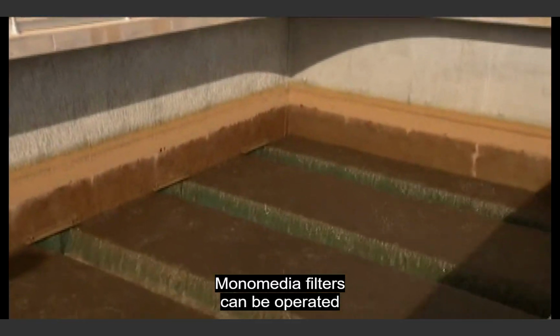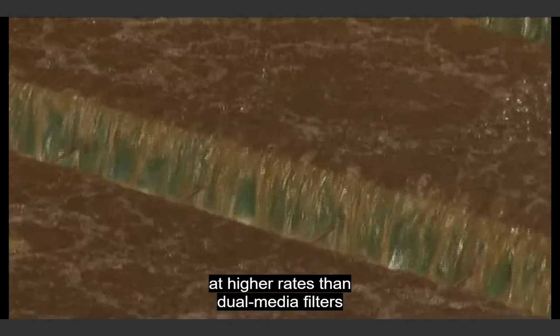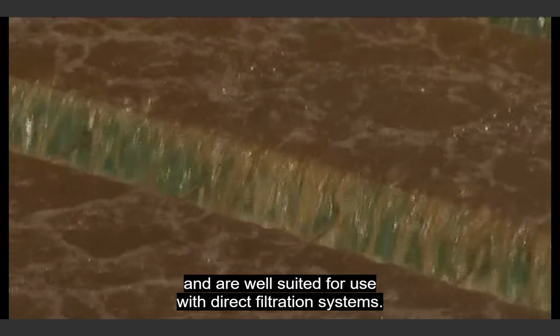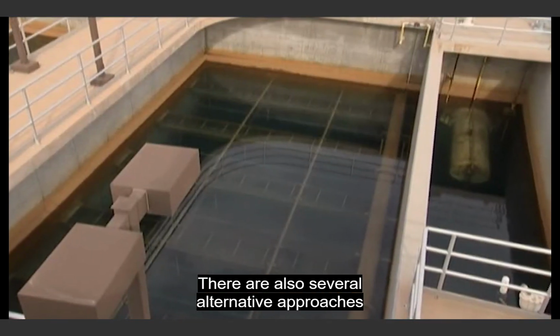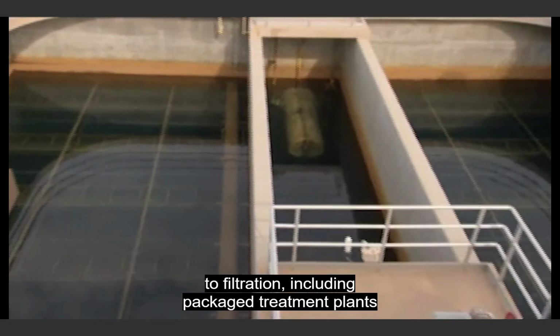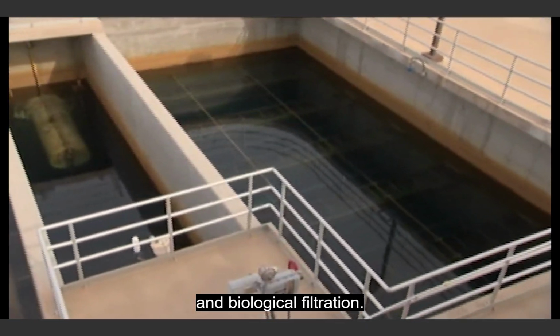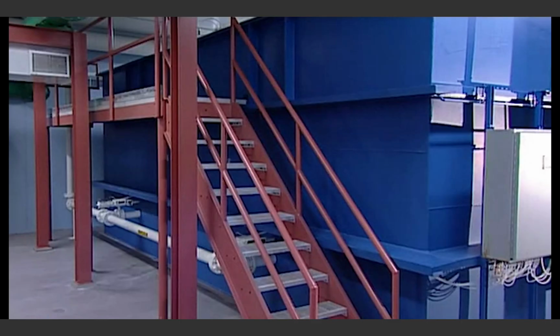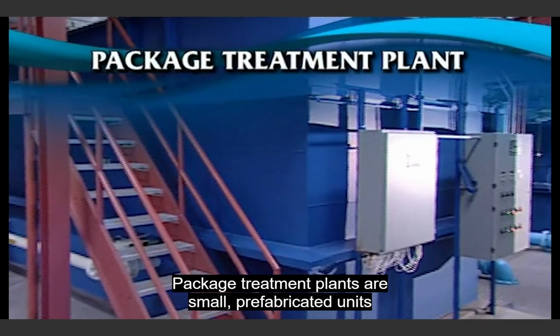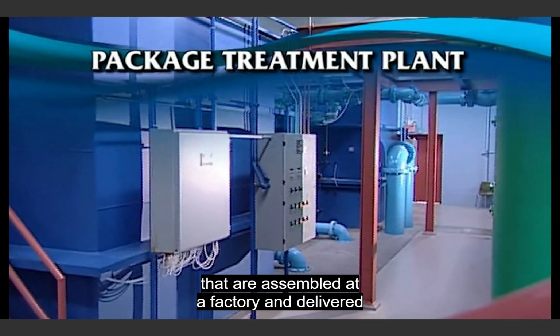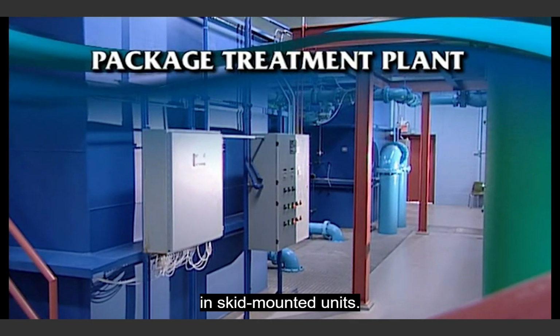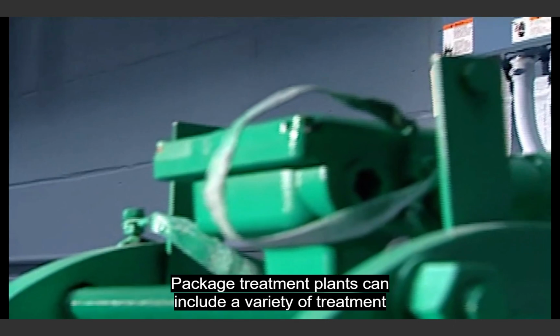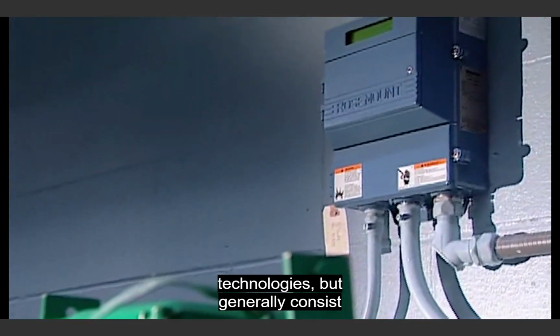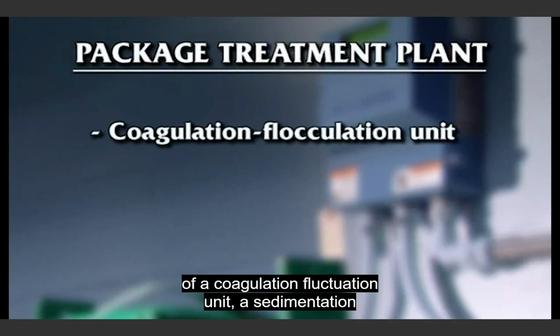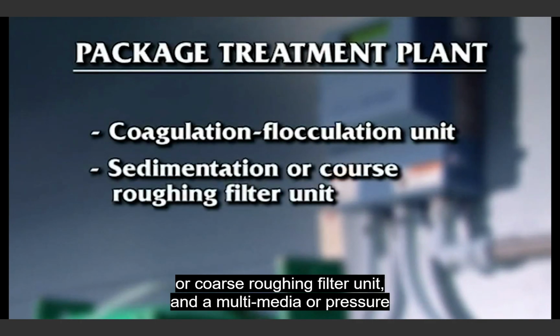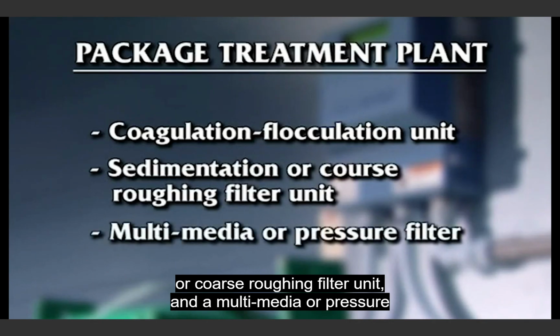Monomedia filters can be operated at higher rates than dual media filters and are well suited for use with direct filtration systems. There are also several alternative approaches to filtration, including package treatment plants and biological filtration. Package treatment plants are small prefabricated units that are assembled at a factory and delivered in skid-mounted units. Package treatment plants can include a variety of treatment technologies, but generally consist of a coagulation flocculation unit, a sedimentation or coarse roughing filter unit, and a multimedia or pressure filter.